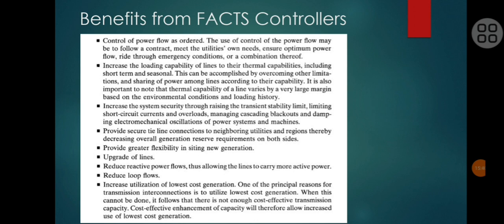Benefits from FACTS controllers, obviously we have seen: control of power flow as ordered, increase in the loading capability of lines, increase in the system security because transient stability limits etc. are increased, and providing secure tie line connections to neighboring utilities, providing greater flexibility in siting new generation, upgrade of lines, reduction of reactive power flows, reduction of loop flows, and increasing the utilization of least cost generation, because basically we are strengthening the transmission interconnections by using FACTS controllers.